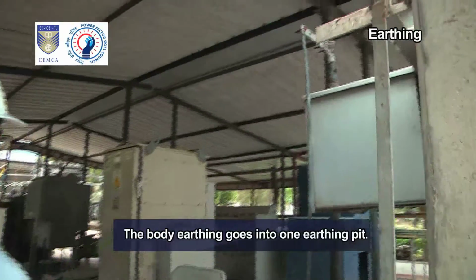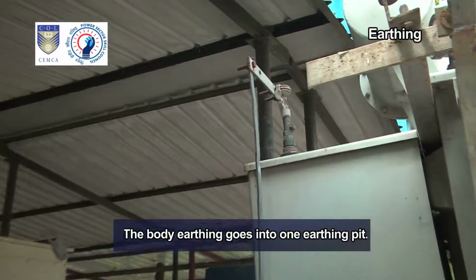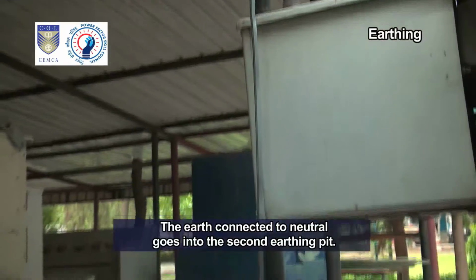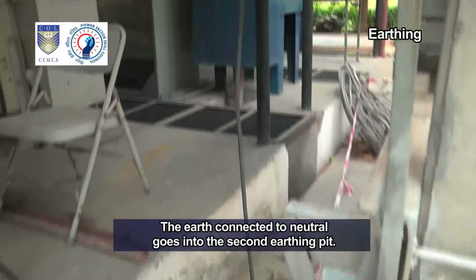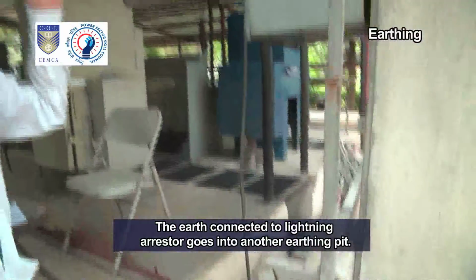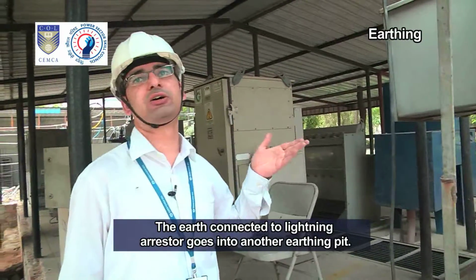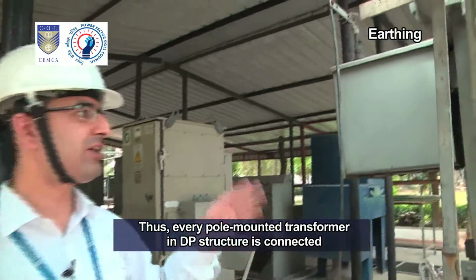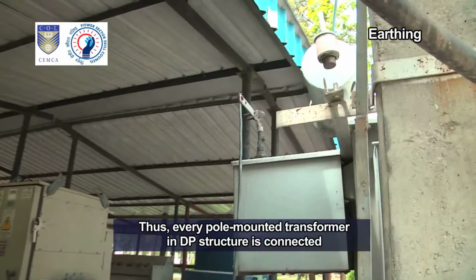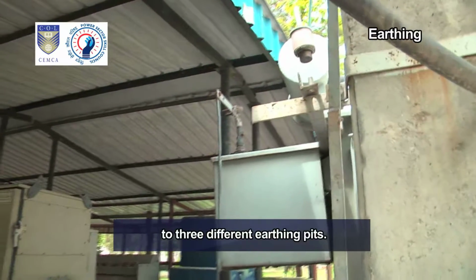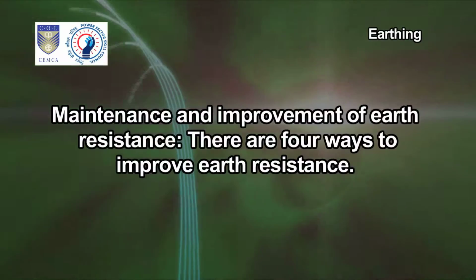The body earthing goes into one earthing pit. The earth connected to neutral goes into the second earthing pit. The earth connected to lightning arrestor goes into another earthing pit. Thus, every pole-mounted transformer in DP structure is connected to 3 different earthing pits.